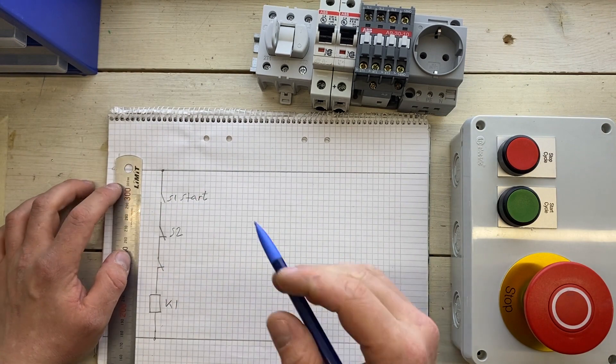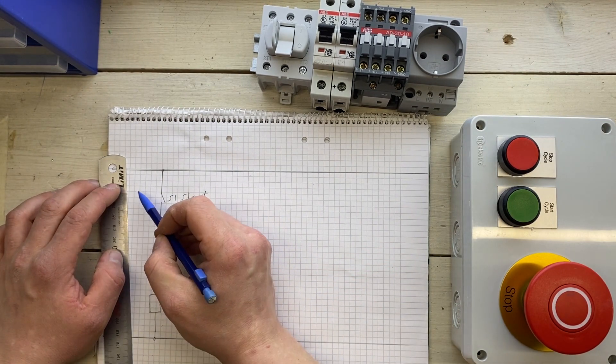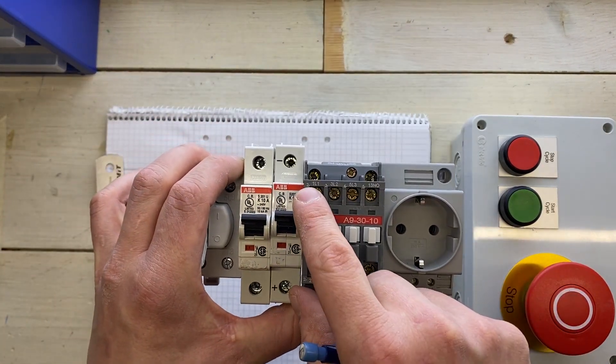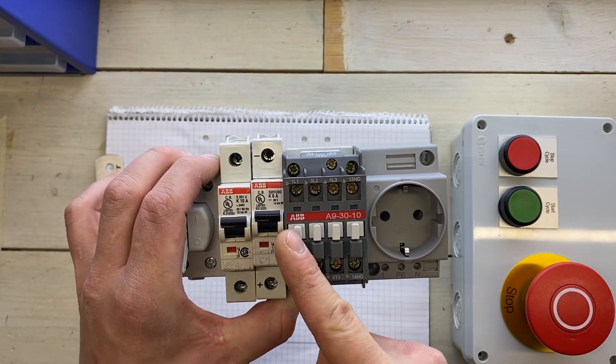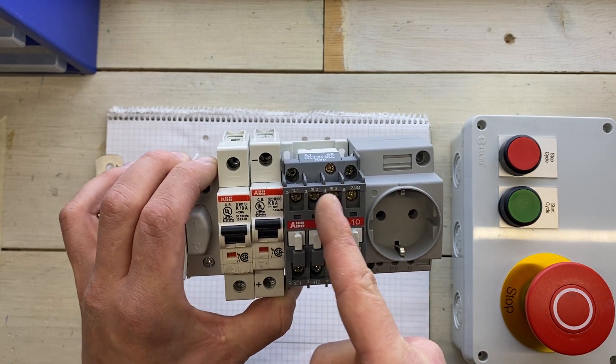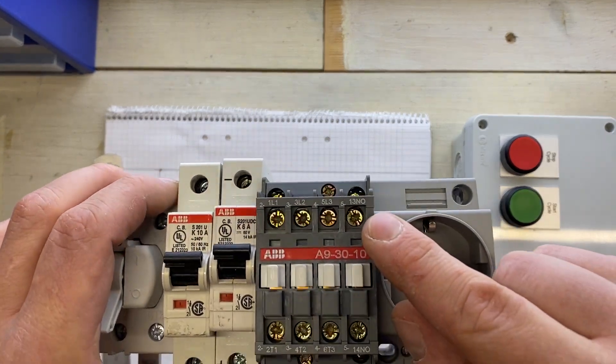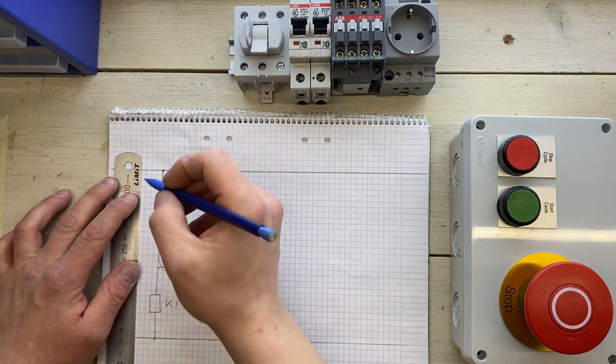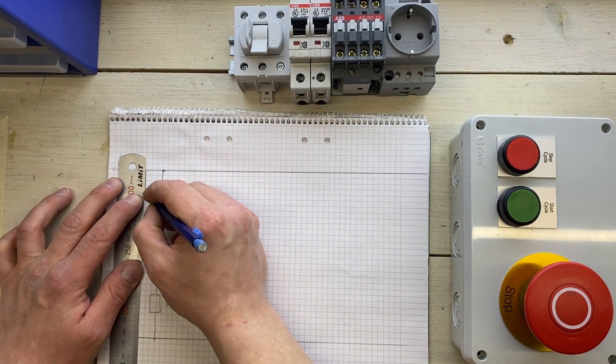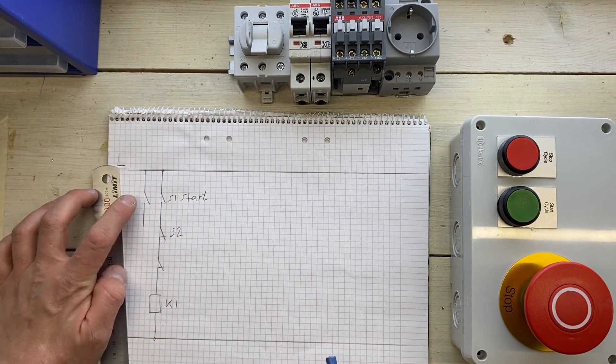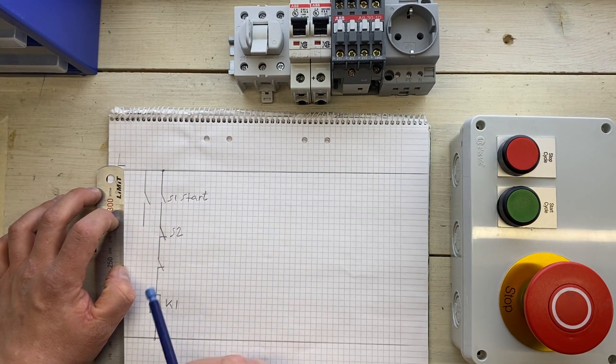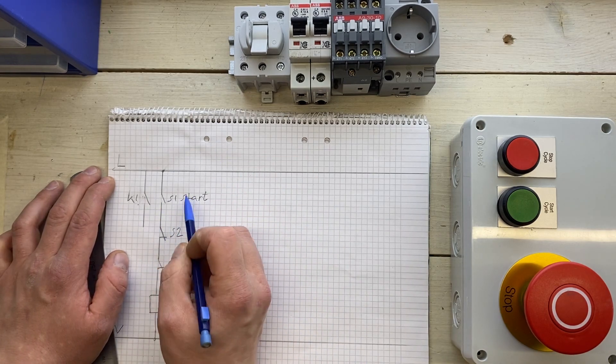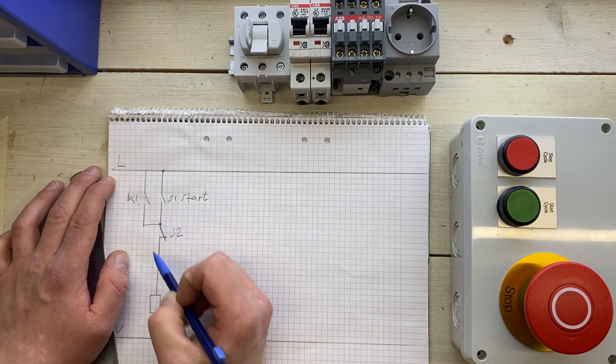So that means we add a redundant contact up here. And as you can see, this one has four contacts in line. And if you run three phase you only need three ones. So you have an extra one that's labeled as normally open. And we will use this one. So we will add another normally open switch. And this one is of course pulled by the relay. That's K1. And if we attach this one in parallel to the S1 start button, like this.